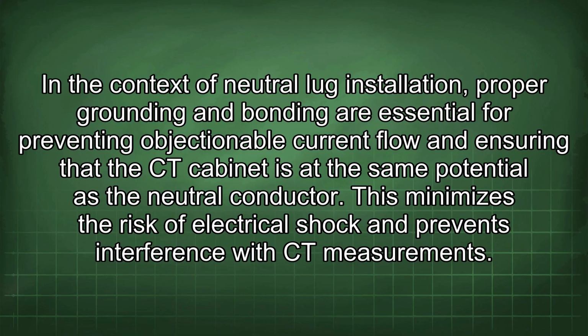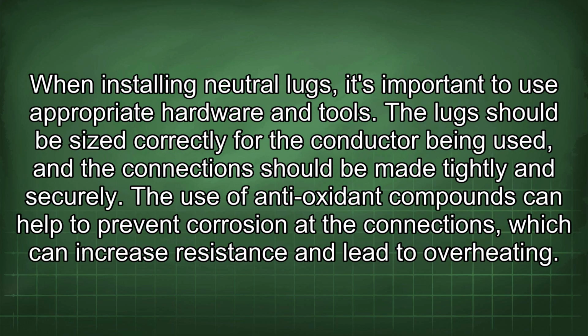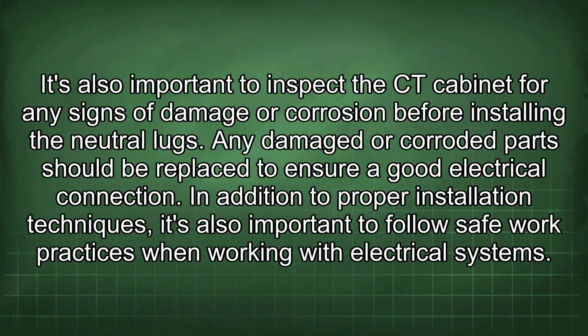In the context of neutral lug installation, proper grounding and bonding are essential for preventing objectionable current flow and ensuring that the CT cabinet is at the same potential as the neutral conductor. This minimizes the risk of electrical shock and prevents interference with CT measurements. When installing neutral lugs, it's important to use appropriate hardware and tools. The lug should be sized correctly for the conductor being used, and the connections should be made tightly and securely. The use of antioxidant compounds can help to prevent corrosion at the connections, which can increase resistance and lead to overheating. It's also important to inspect the CT cabinet for any signs of damage or corrosion before installing the neutral lugs. Any damaged or corroded part should be replaced to ensure a good electrical connection.